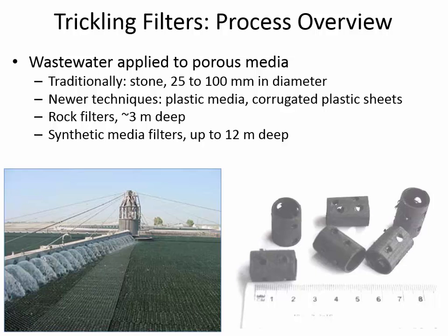This is all about getting the bacteria a surface to grow on. And so if you use large stones, the surface area of that stone is much less than if you have small media that has holes drilled in it. Everything we want to do is maximize the surface area. And the other advantage is it's quite light. Those heavy rocks, we can only have a pile of maybe 3 meters of rocks before the support structure really has to be enormous. But if it's a pile of plastic pellets, we can maybe make it 10 meters tall, and still it's going to be very light at the bottom.